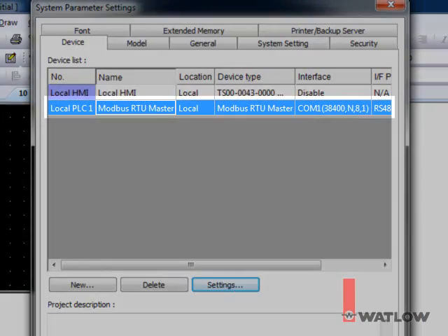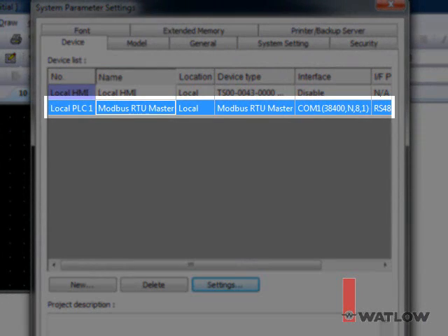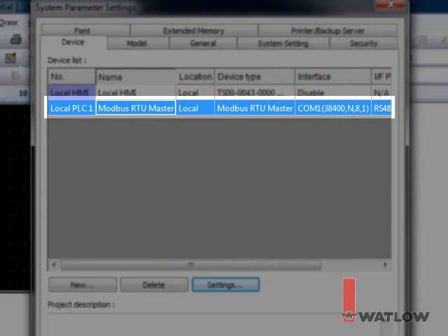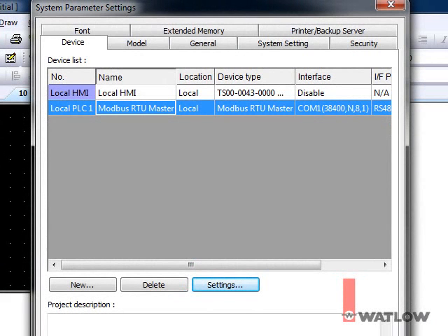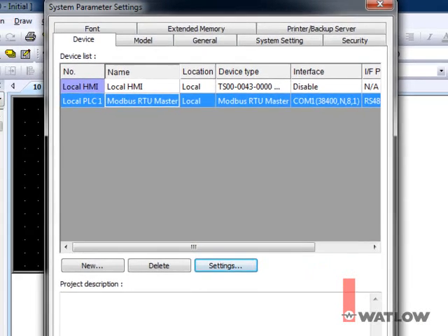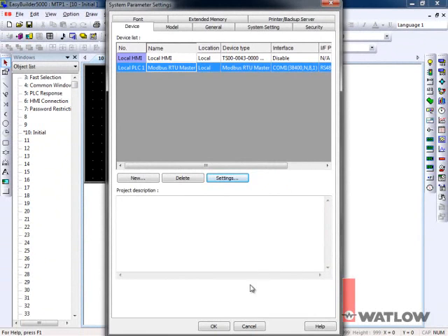Note that there's only one Modbus RTU Master in the device list, even though we plan to communicate with two RM modules. That's because both RM modules are on the same network. We've configured this Modbus RTU Master to operate the OIT's COM 1 port, so it will be the master on the network that we connected to that port. Click OK.